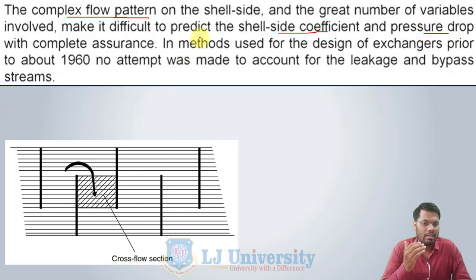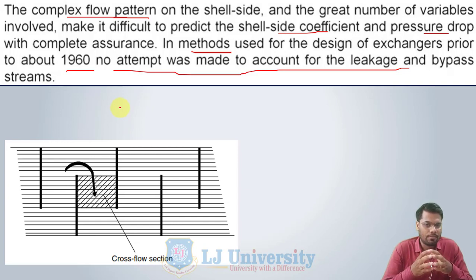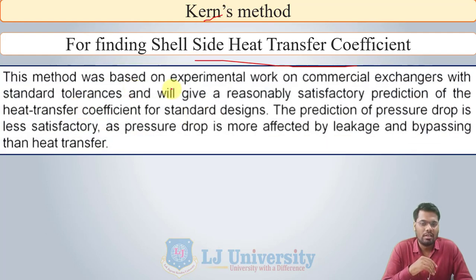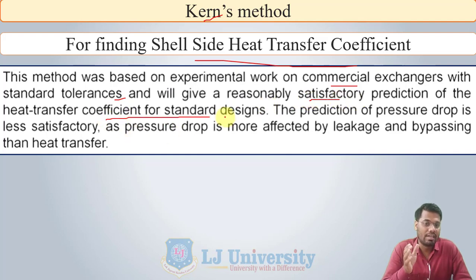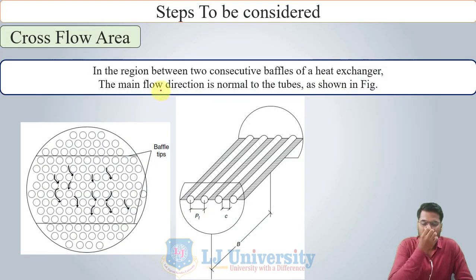In Kern's method — the first method — used for the design of exchangers prior to about 1960, no attempt was made to account for the leakage and bypass streams. So in Kern's method, there is no consideration of leakages and bypasses. This method was based on experimental work on commercial exchangers with standard tolerances and will give reasonably satisfactory prediction of the heat transfer coefficient for a standard design. The prediction of pressure drop is less satisfactory, as pressure drop is more affected by leakages and bypassing than heat transfer.